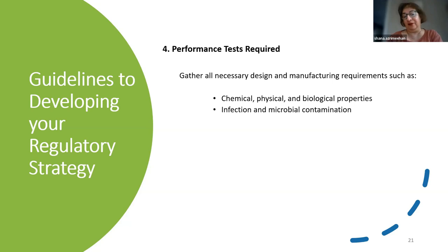And that could be another thing that you have to be aware of: does the product have extractables or leachables that are potentially toxic to cells? So you have a whole testing regimen which depends on your type of device. And you have to also take into consideration the method of sterilization. For instance, if it's sterilized by ethylene oxide, are there any residuals? So it's not only performance per se, but it's also looking at the characteristics of the device, and safety is a very critical component.